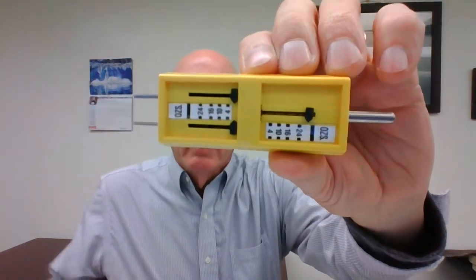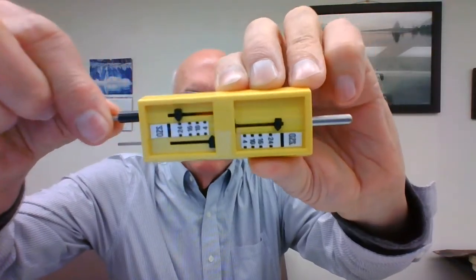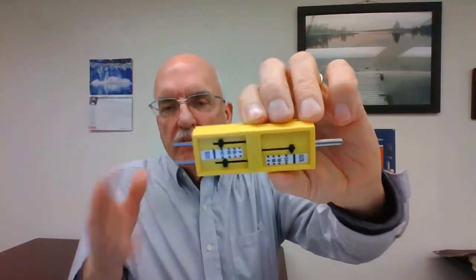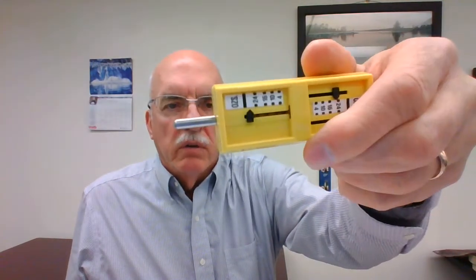Talking about that sloppy receptacle, I mentioned this tension checker in the last session that I gave, and I'm just going to mention it again. This is a wood head tension checker. You set the indicators to 0, and then when you pull it out of the wall, it'll tell you how much tension was on there, and they give you parameters that come with the tester. They'll tell you what readings to look for, and they have the ground pin also. So I'm going to talk about that more in the next session, which is receptacles.